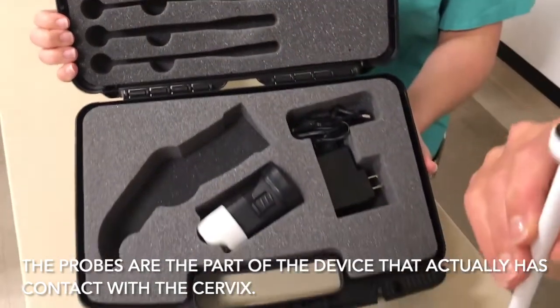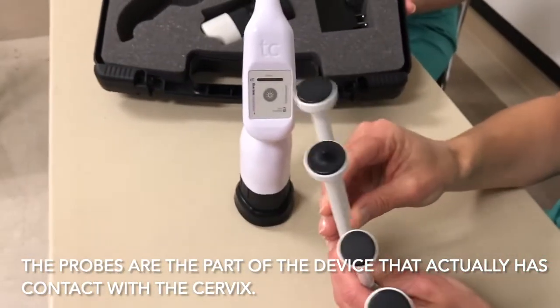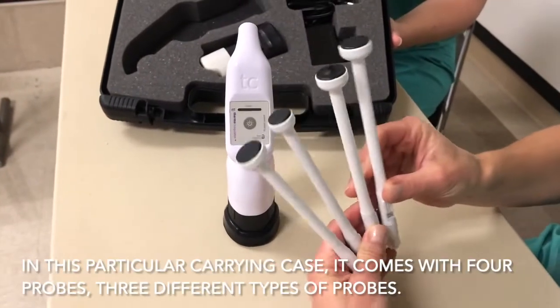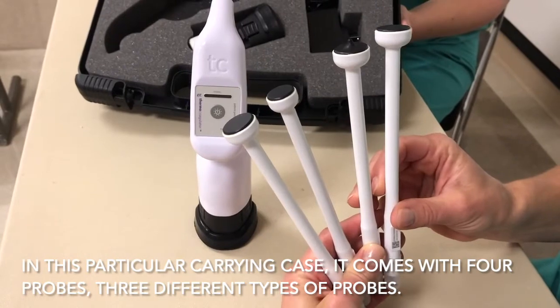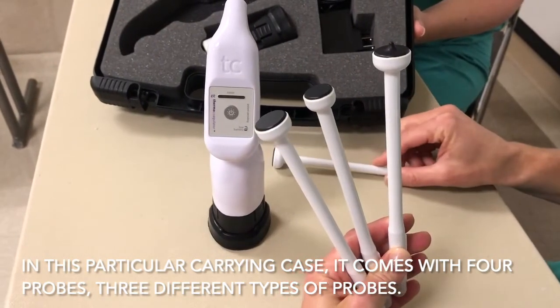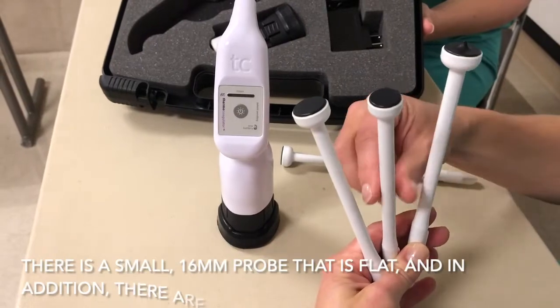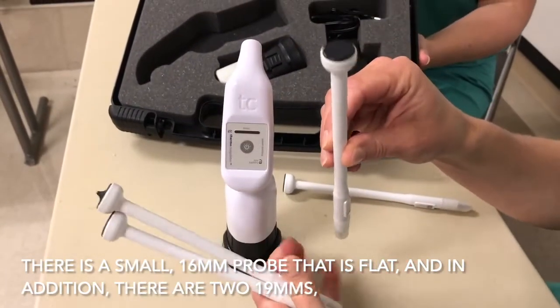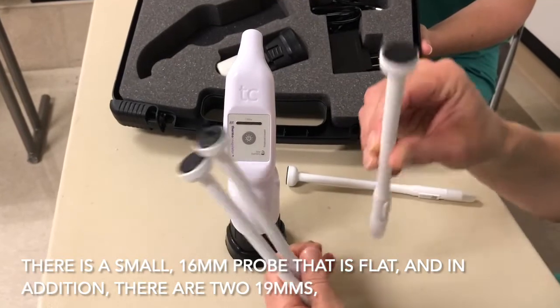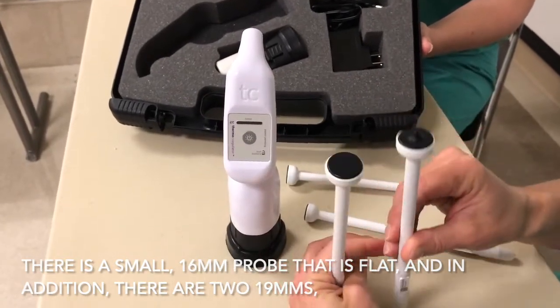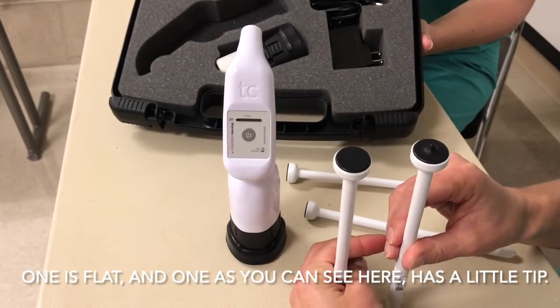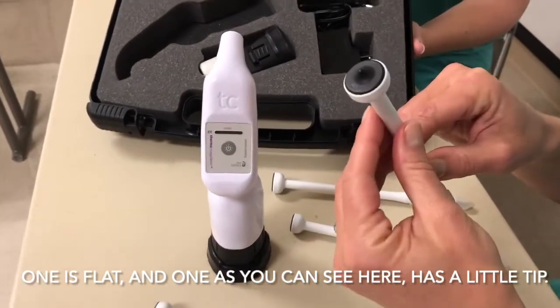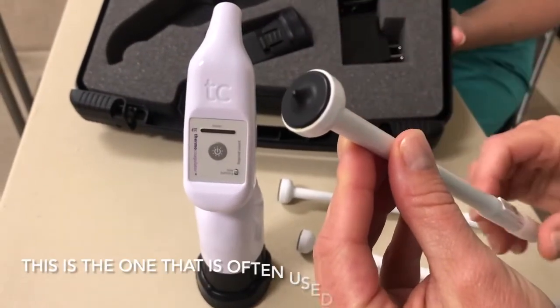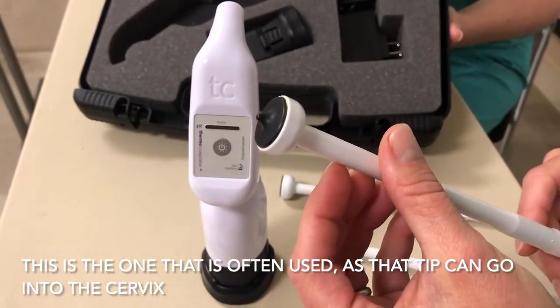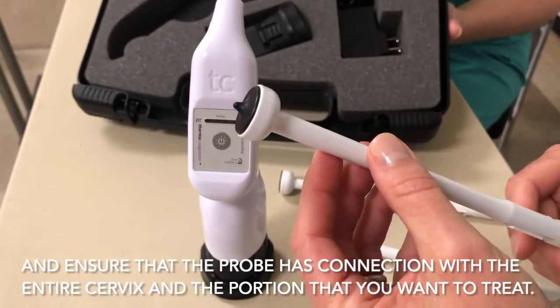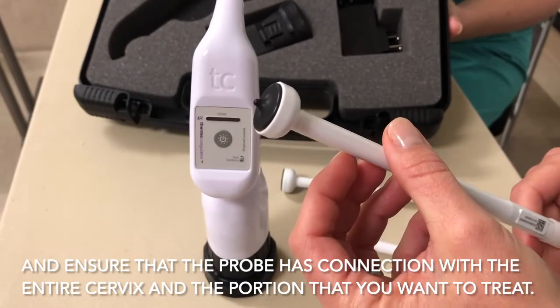The probes are the part of the device that actually has contact with the cervix. In this particular carrying case, it comes with 4 probes, but 3 different types of probes. There is a small 16 millimeter probe that is flat, and in addition, there are 2 19 millimeters. One is flat, and one, as you can see here, has a little tip. This is the one that's often used, as that tip can go into the cervix and ensure that you have connection with the entire cervix and the portion that you want to treat.